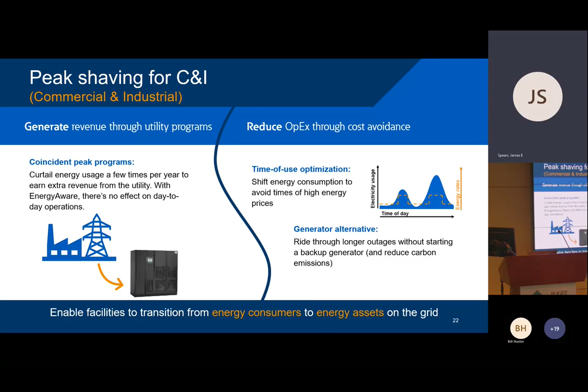We've talked about some of the things you can do with this technology, and it doesn't require anything special from a hardware perspective: lithium batteries, traditional UPS, and some special controls that fit in a box about 18 inches square, either on top of the UPS or on the wall next to it.